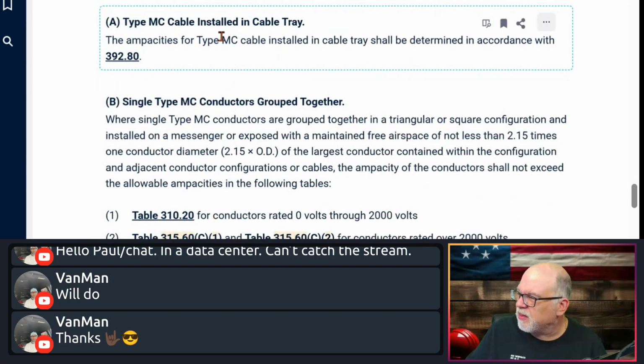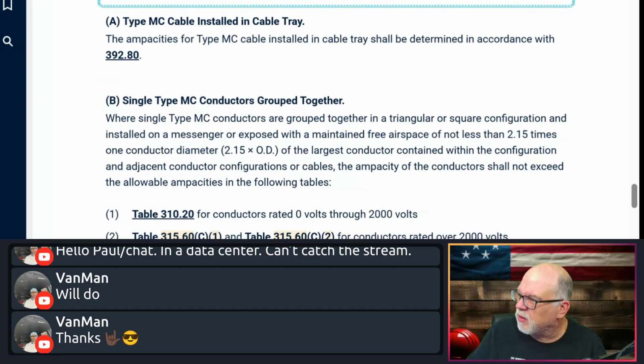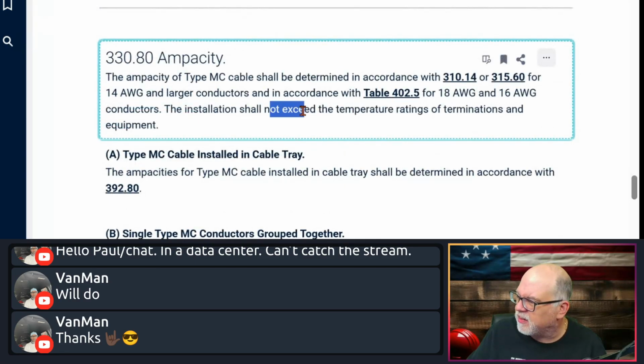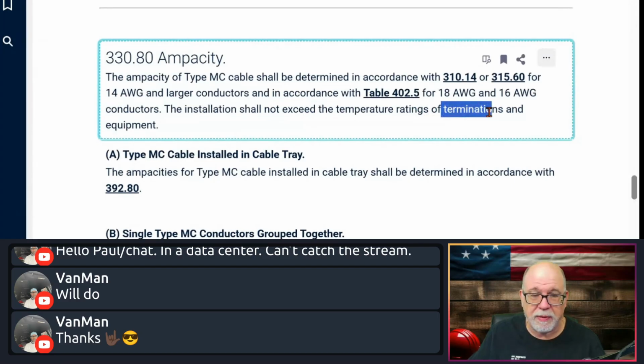So MC cable that's installed, it says the installation shall not exceed the temperature rating of the terminals and the equipment. Absolutely right. So even though the conductors inside of that MC cable may be rated 90, wet or dry, THHN/THWN-2 or XHHW-2, at the end of the day the temperature rating of the terminals or the equipment is going to come into play. Typically the terminals are probably going to be 75 or 60, probably more 75 today, right? And a lot of your equipment is probably going to be defaulted at 75-degree termination. So using the 90 for adjustment and correction is very common for us in wiring methods.